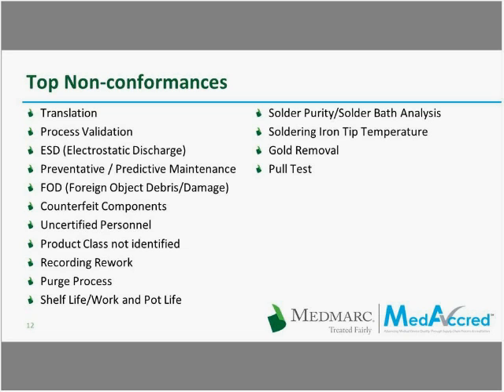Product class not identified—is it class 2 or class 3? Recording rework: excessive rework can lead to solder joint failure and a fraudulent device history record. A lab can tell by the thickness of the intermetallic bond if a solder joint was heated repeatedly. So we stand back and watch the solderers as they work, and if we see them hit that solder joint a third time without writing it up, that would be a non-conformance.